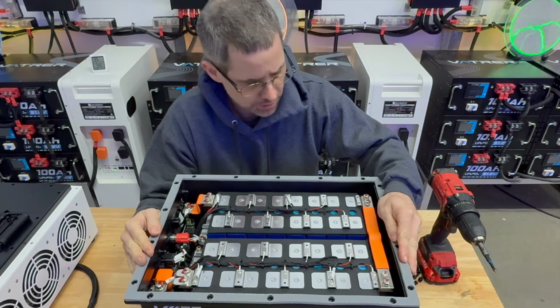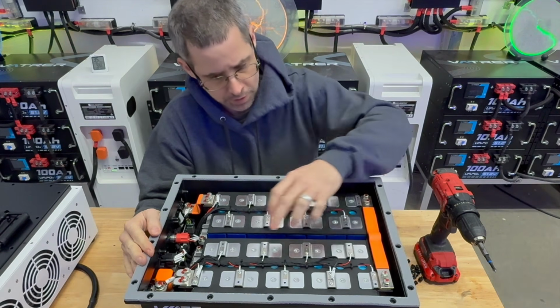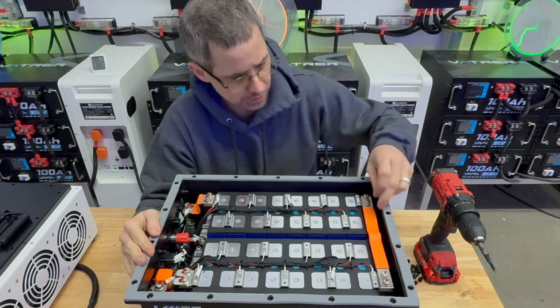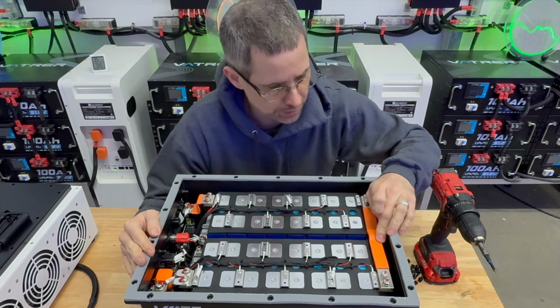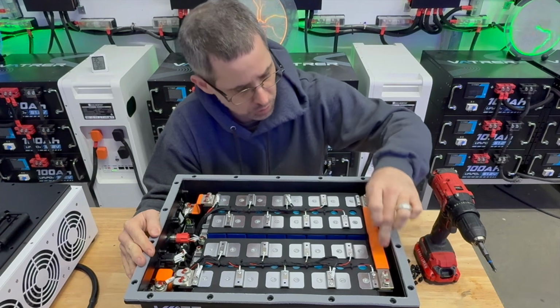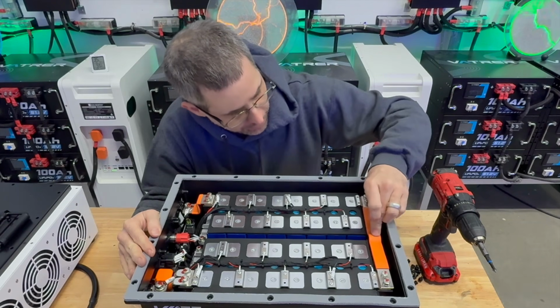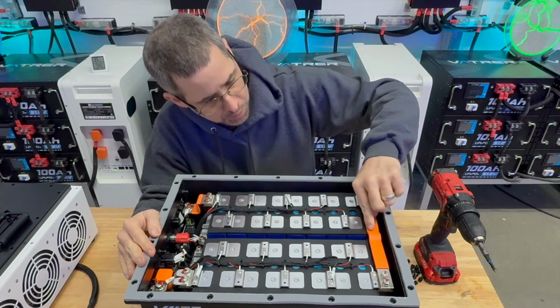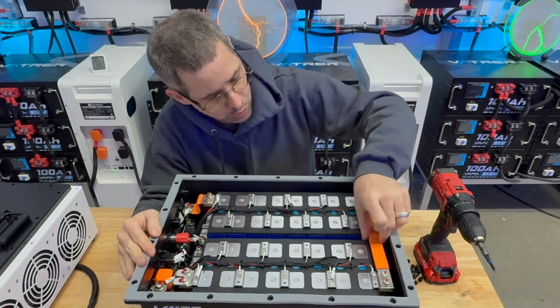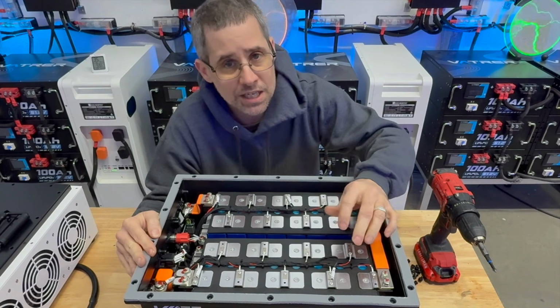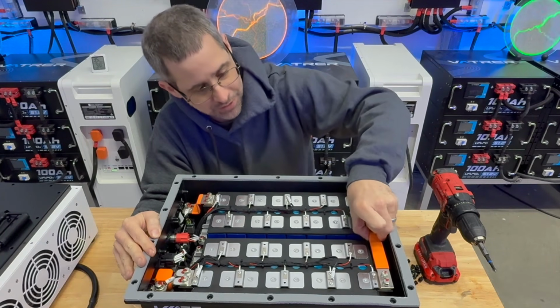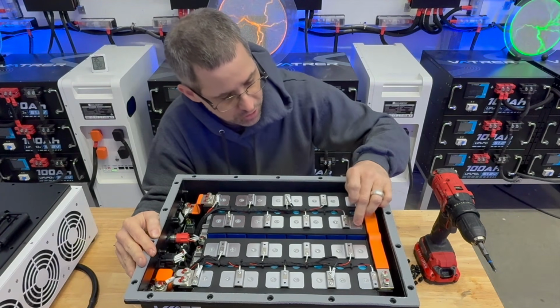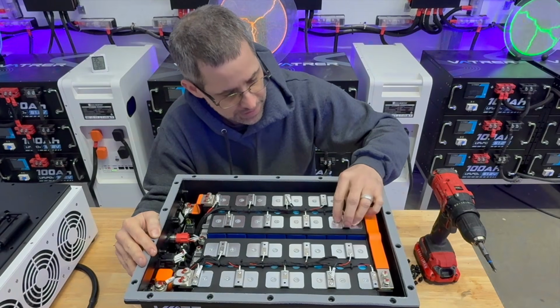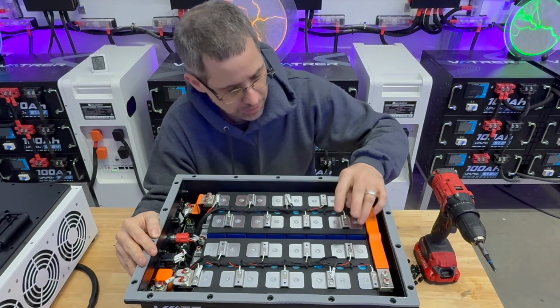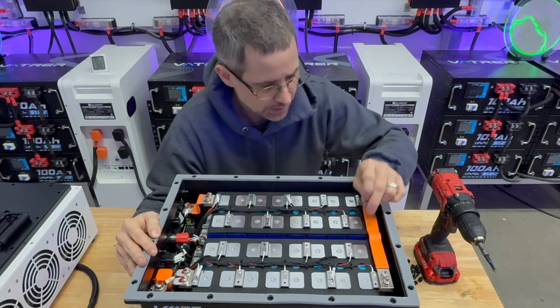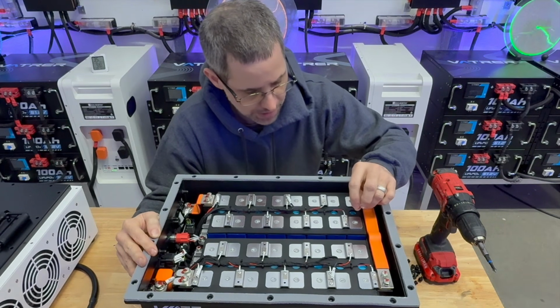Okay, so it's your typical 16S configuration. You can see the set of cells on one side, and on the other side there's this big gnarly bus bar connecting them. I like how they have it connected with 2 bolts on each side. It's a very thick copper bar, but they even put a relief in the center of the rigid cable, which is nice because as the cells expand and contract, this is going to do the same. As all the cells are connected together, you also have that hump so it can adjust without breaking the welds. These are nice laser welds you can see here.